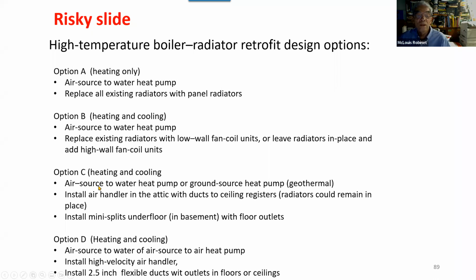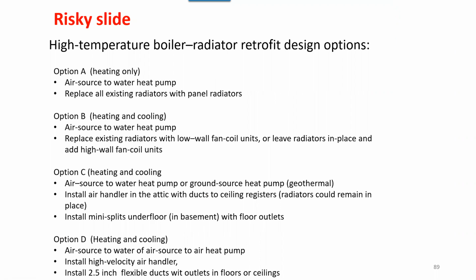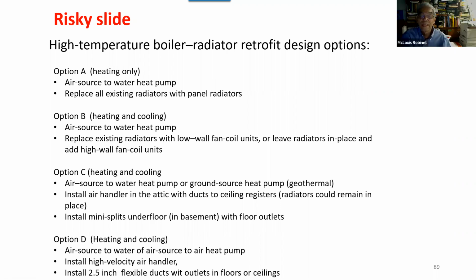Another option would be to use an air source to water heat pump or a ground source heat pump, and you'd install air handlers. Say you have an attic that you're not physically using as a living space, you could put an air handler in the attic and then use short ducts to different rooms. You provide registers in the ceiling, and that would be the simplest way, say for the second floor. You would also provide mini splits, say in a basement between the joists, and provide holes in the floor, whatever, to provide heating and cooling. That would be one option.